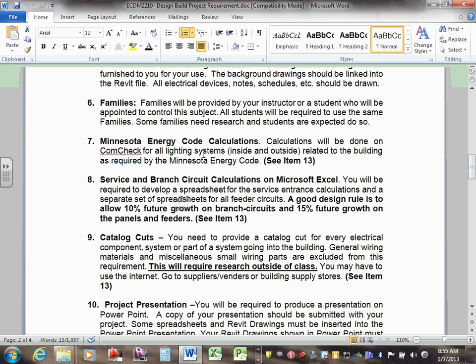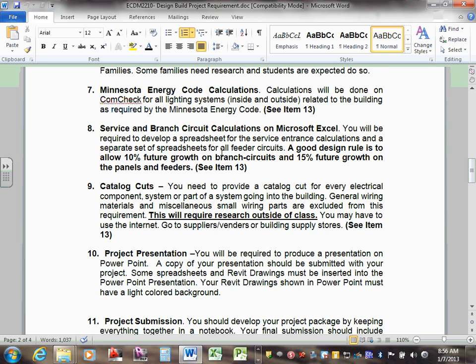Okay, Minnesota Energy Code, my friends — we're going to see how to do Minnesota Energy Code, inside and outside. Service and branch calculation: as you do your calculation, whom am I going to pick on? Brian, do you see that one? It says good design is 10% future growth on the branch circuit and 15% future growth on the panel and feeders. So as you do your load calculation, at the end, on the feeders you add 15%. So when you do your calc and come up with 55 amps, say, you multiply it by 1.15 for future expansion.